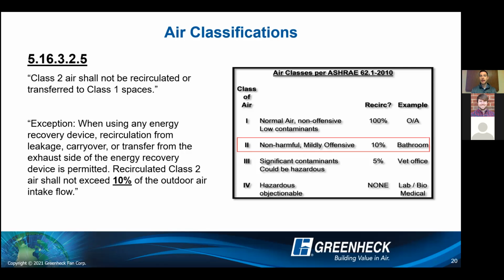So even if you did have a purge wheel and you reduced that cross contamination, you still get that 1% or 2% cross leakage. So you still could not use that in your class 4 applications. So again, while they are used, while we will offer them via special design, it's not going to help you get into an application with or without it. It's going to be the same exact class 1, 2, and 3 allowance. So hopefully that makes sense.